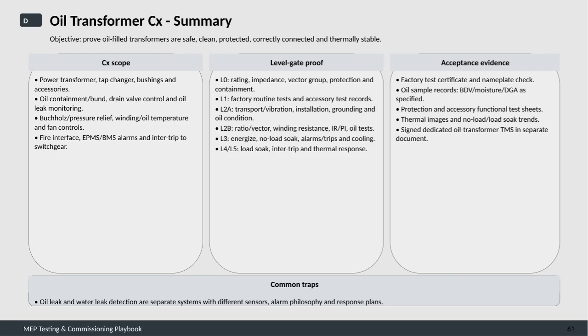The primary objective here is to ensure that these transformers are safe, clean, properly protected, correctly connected, and thermally stable. This is critical to guarantee reliable operation and prevent any potential failures. The scope of commissioning covers several key components. We focus on the power transformer itself, including the tap changer, bushings, and all related accessories.